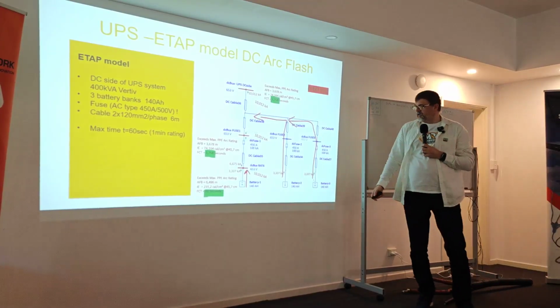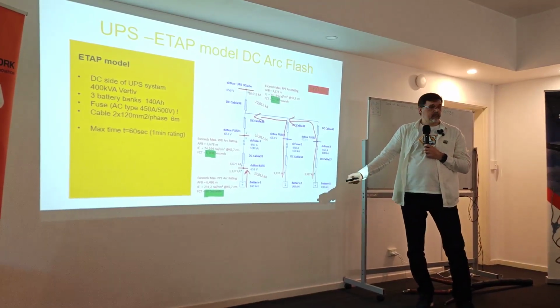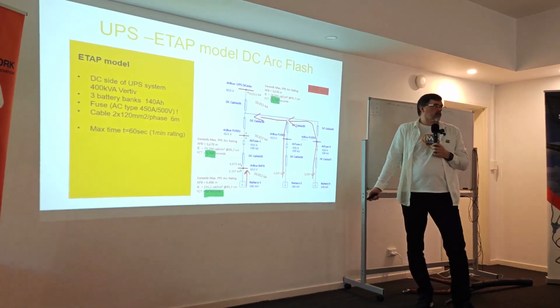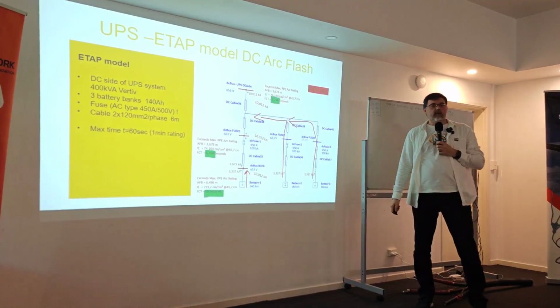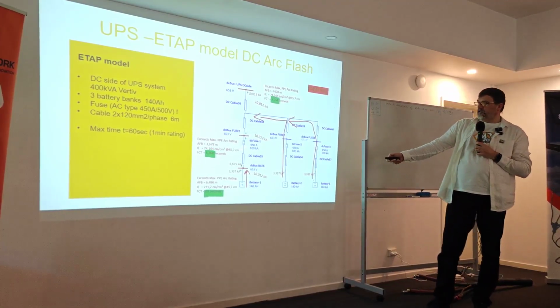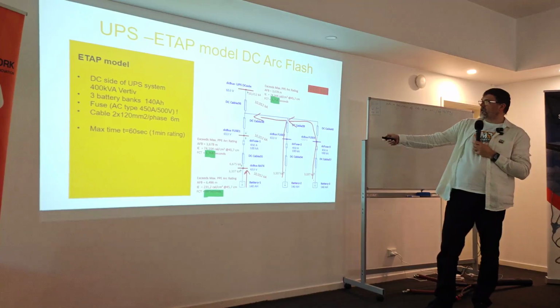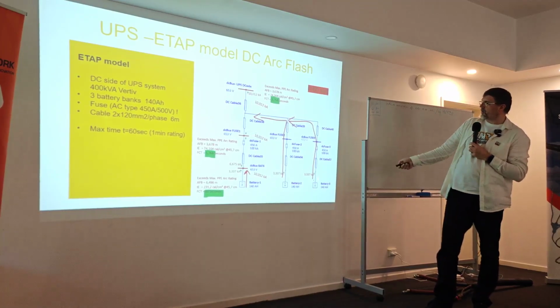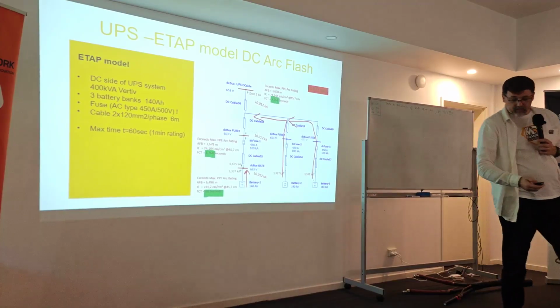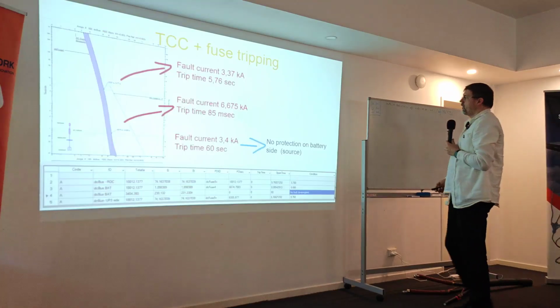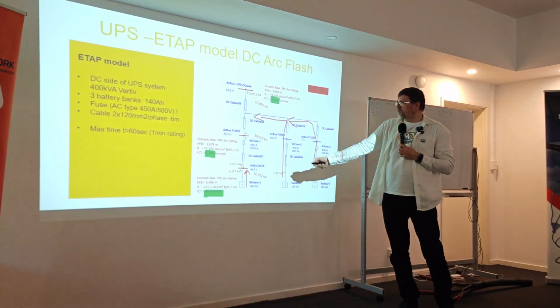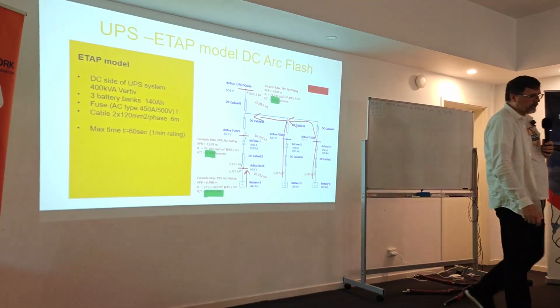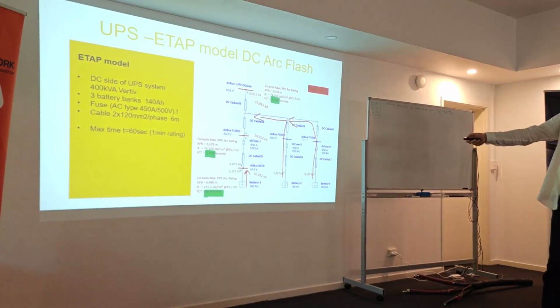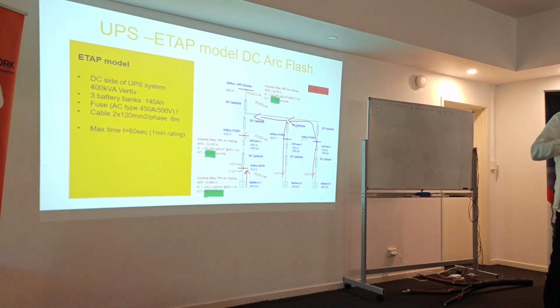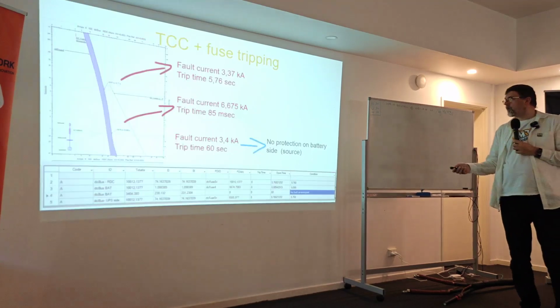If you increase it to 60 seconds, you can see this didn't trip at all, because it's a battery; a battery will not trip. It will keep going until it can. The fuse will actually trip in 5.7 seconds. That was the first surprise. Then you have the same time because they keep going from the same three levels. So you see that 5 seconds is the tripping time, or what we calculated. But you need to get the cables right, because if you don't, the calculation might be off, especially if you have short cables. This will influence the DC calculations a lot.